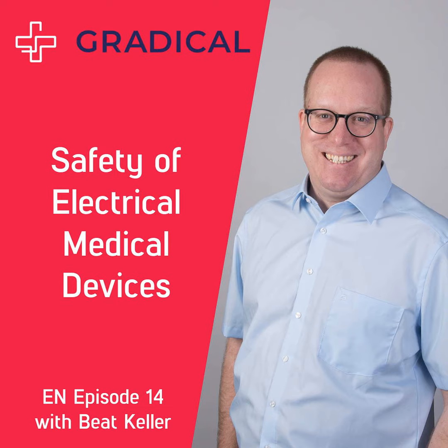But I don't understand now, where do we really need the V0 then? You won't find the V0 - you can create in general a medical device with V1 and V2 components. Also, there's another section about flammability of secondary circuit materials, in the single fault condition section 13.1, where we have the requirement that the secondary circuit is mounted on V1 material, not V0. So actually for electrical and electronic devices, at least in medical devices, you don't need V0 materials - is that correct? In the general standard, you can find it, correct.